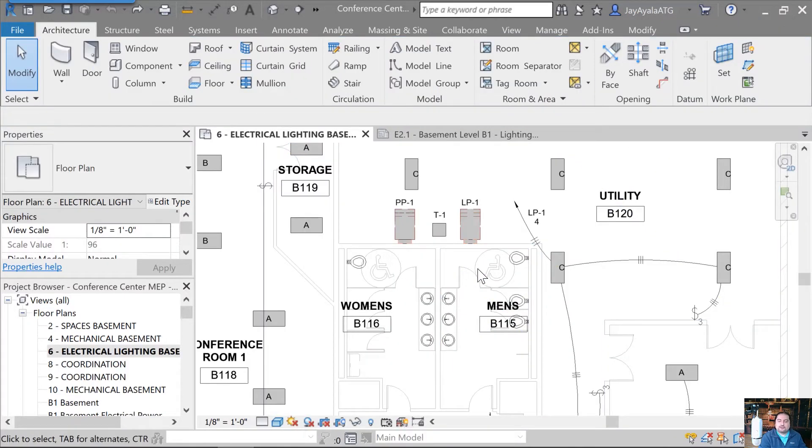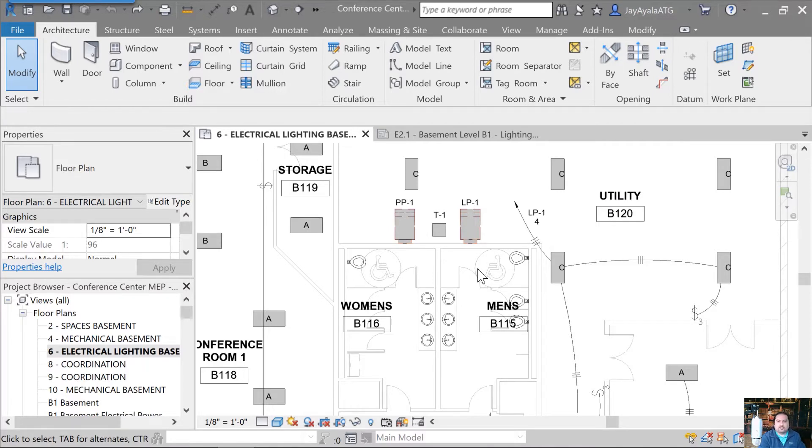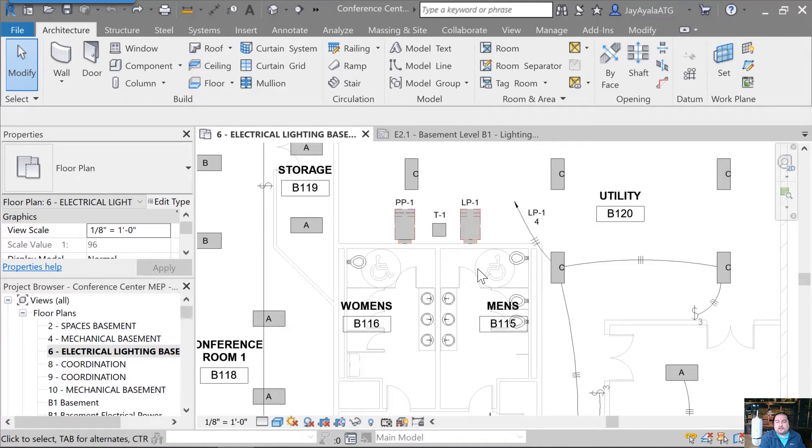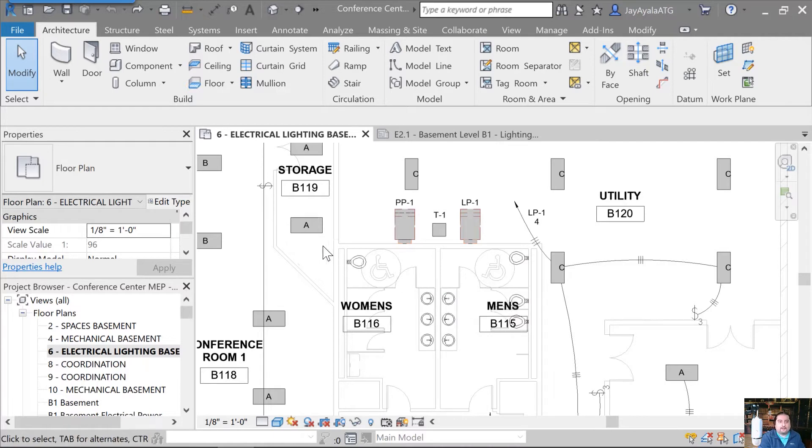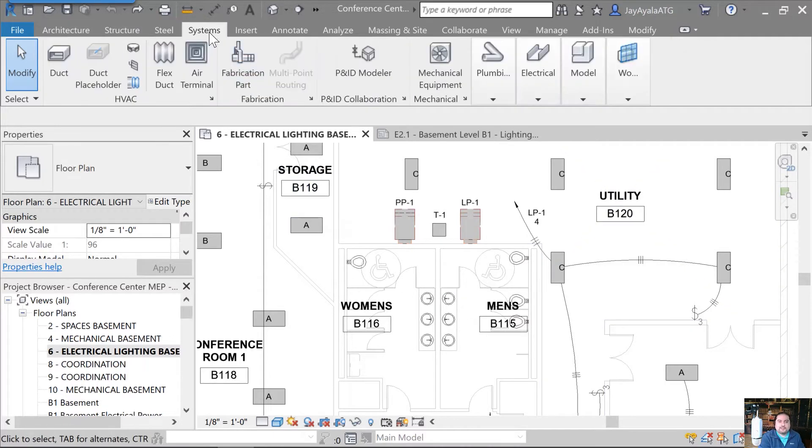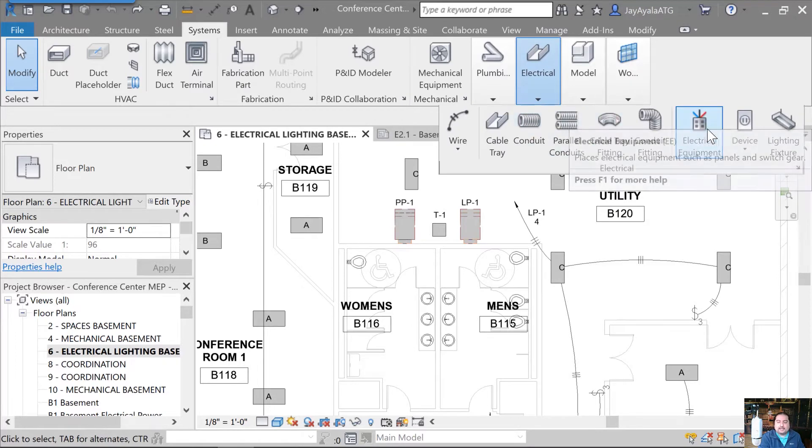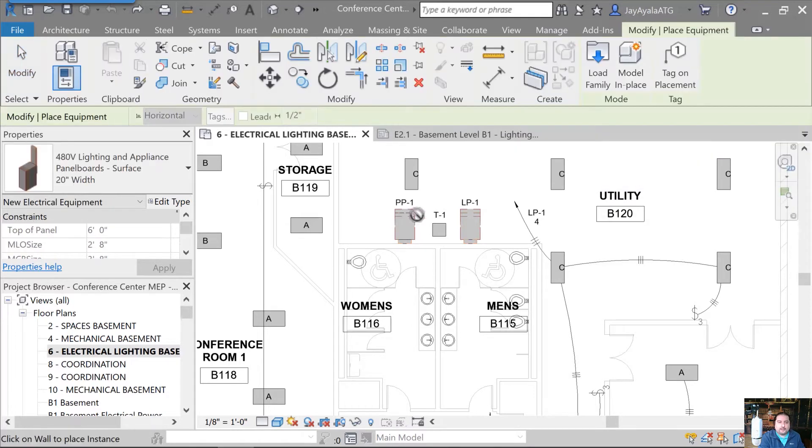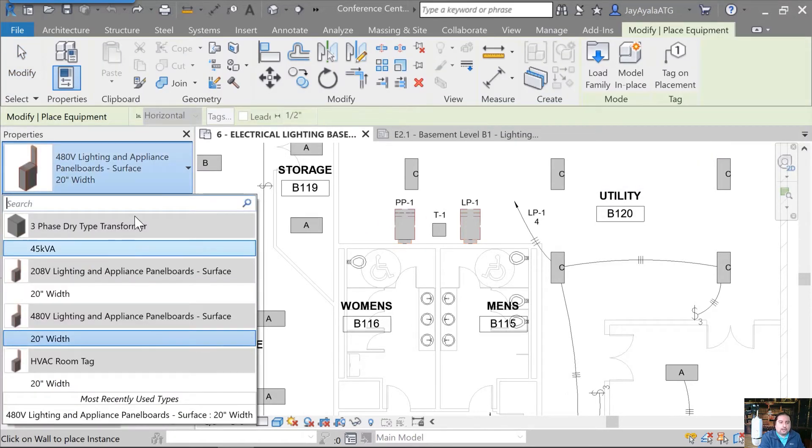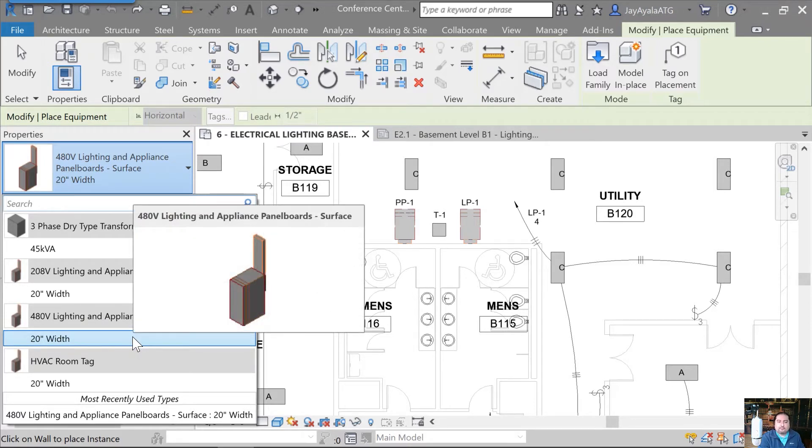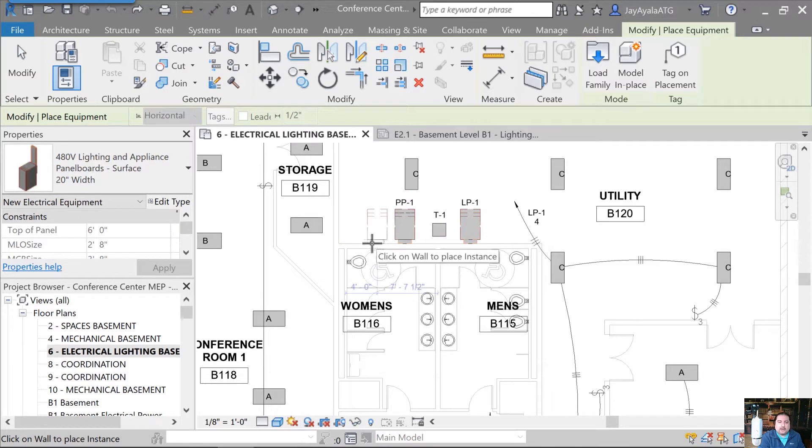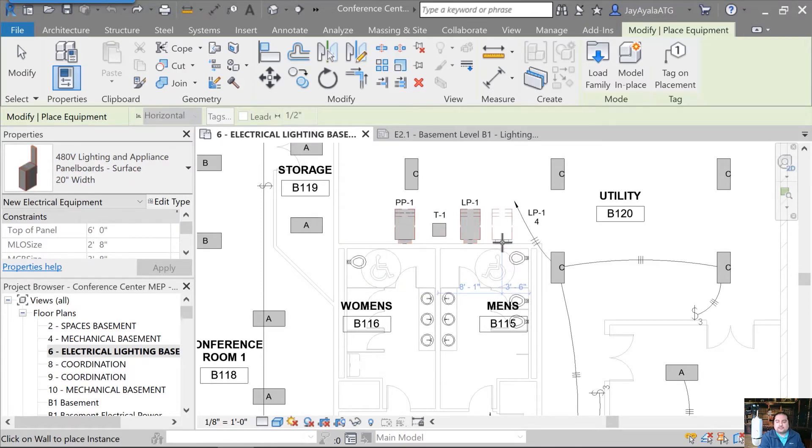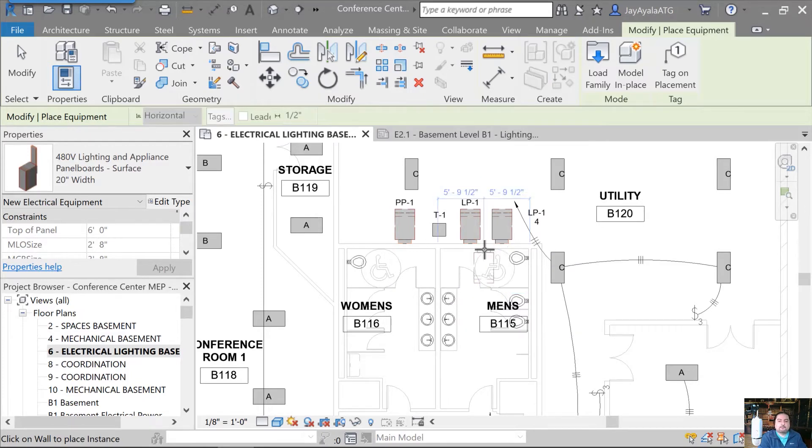So starting from scratch, if you're working on laying out your devices and your lighting fixtures and things like your duplex receptacles, one of the things you may not know with Revit for electrical is that we can actually add a lighting panel that's smart. All of the circuitry information on that panel can be added directly there. So here's how we start. From the systems tab, we'll go to the electrical and we can add electrical equipment. And in here, we're going to look at the 480 volt lighting power panel. And based on how we have set this up, this particular panel needs a surface wall hosting. So we can place that right there.